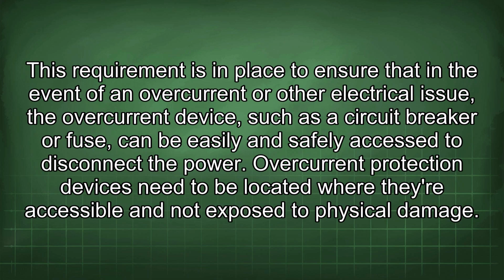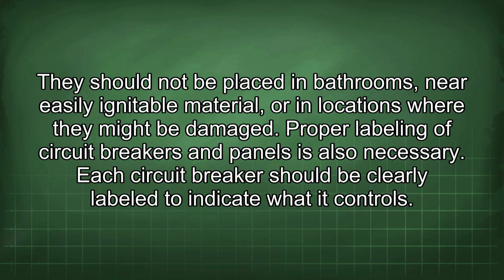This requirement is in place to ensure that in the event of an overcurrent or other electrical issue, the overcurrent device, such as a circuit breaker or fuse, can be easily and safely accessed to disconnect the power. Overcurrent protection devices need to be located where they are accessible and not exposed to physical damage. They should not be placed in bathrooms, near easily ignitable material, or in locations where they might be damaged.